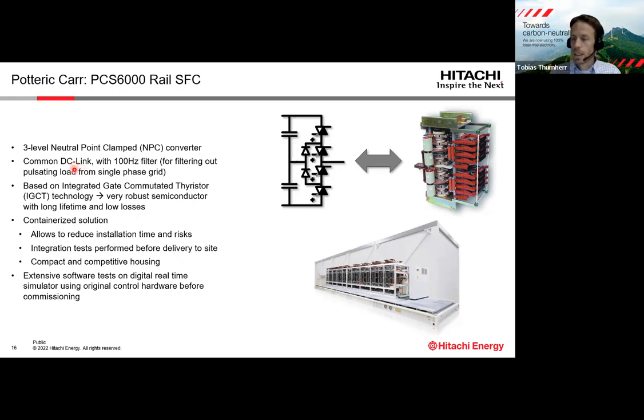We have a common DC link with this technology, and there is a 100 Hertz filter connected to this DC link. The reason for that is that with a single phase load, there is actually a pulsating load that has twice the fundamental frequency. So in this case, it's 100 Hertz. And basically, you will see an oscillation in the DC link with these 100 Hertz. And with a passive filter tuned to 100 Hertz, this oscillation can be reduced.